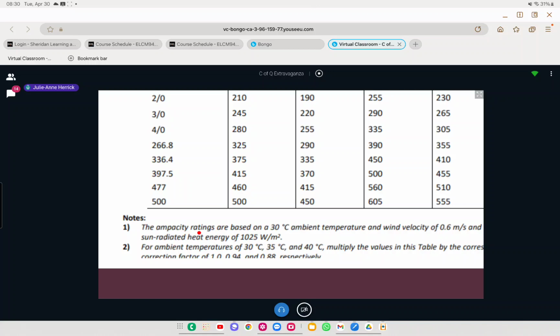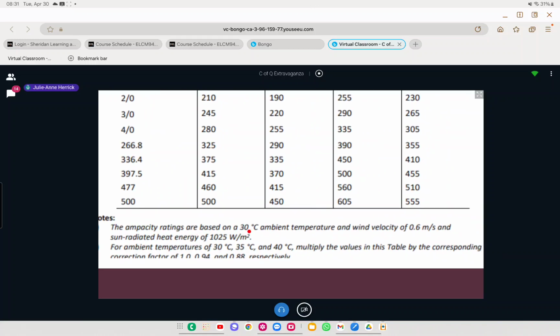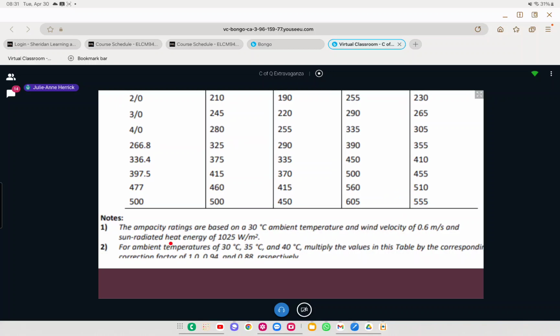Always check your notes. The ampacity ratings are based on 30-degree ambient temperature and a wind velocity. If the ambient temperature is different, you have to do a quick multiplier. Same if the wind velocity or the sun radiated heat energy is different. So again, always check your notes.